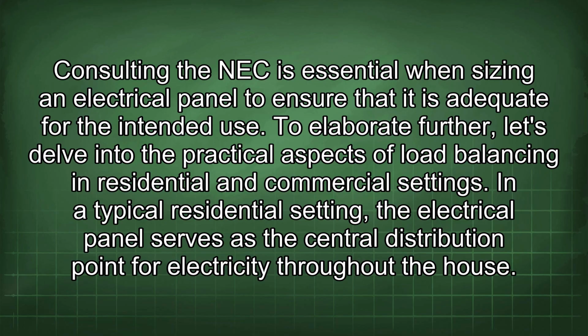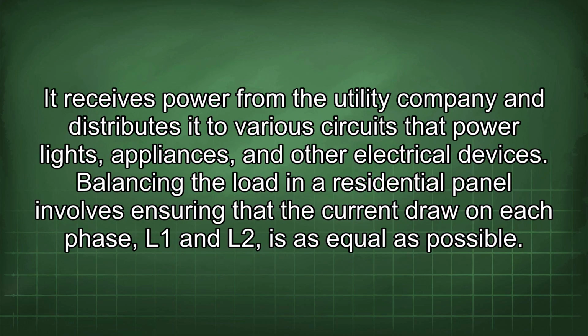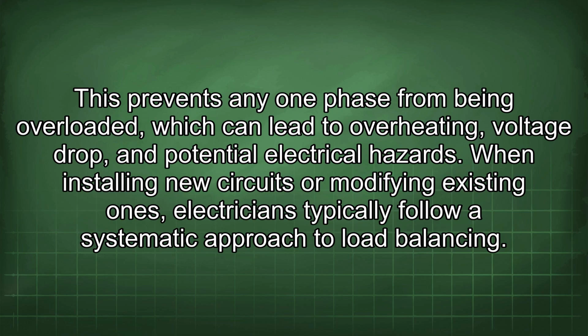In a typical residential setting, the electrical panel serves as a central distribution point for electricity throughout the house. It receives power from the utility company and distributes it to various circuits that power lights, appliances, and other electrical devices. Balancing the load in a residential panel involves ensuring that the current draw on each phase, L1 and L2, is as equal as possible. This prevents any one phase from being overloaded, which can lead to overheating, voltage drop, and potential electrical hazards.